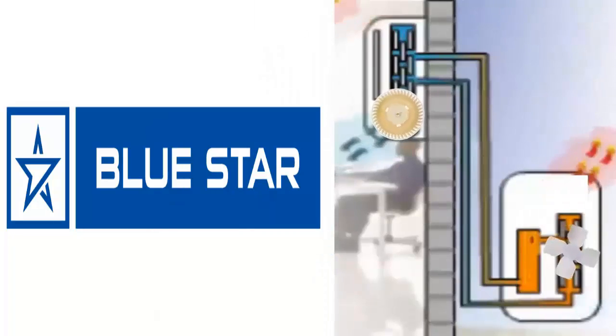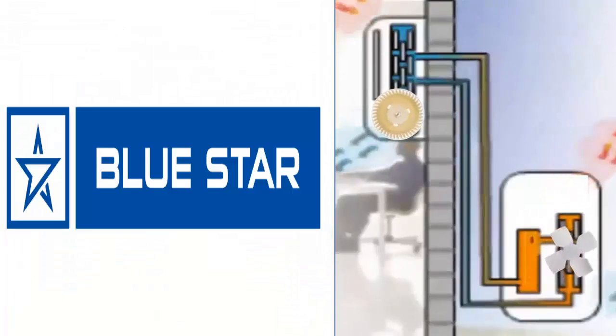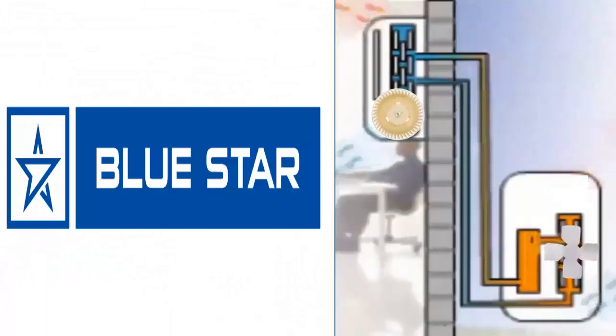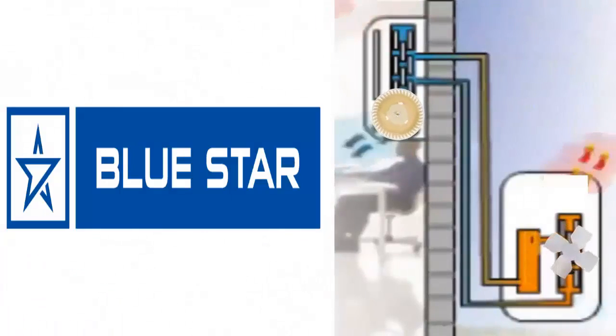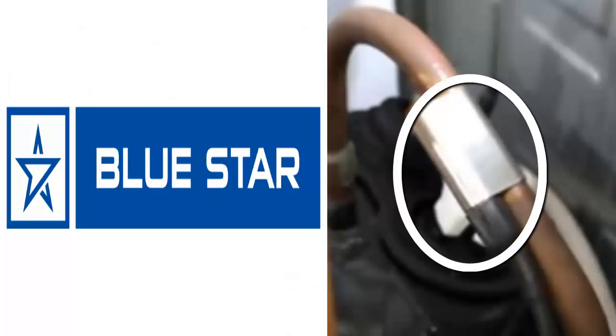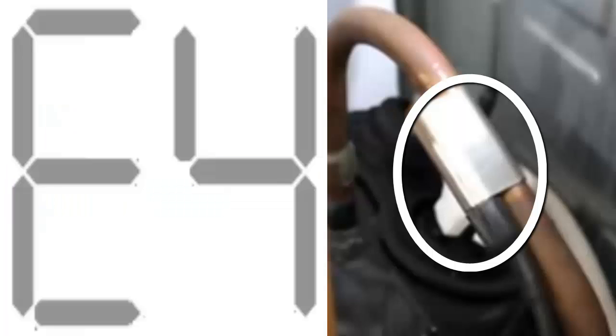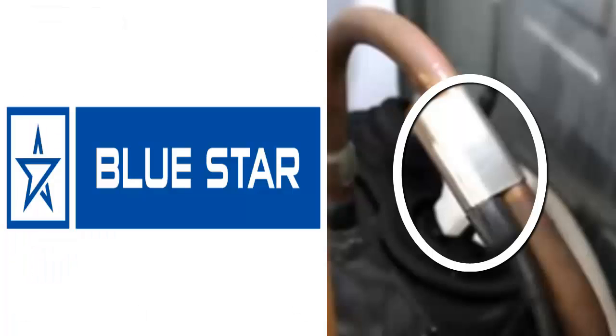Code F5 indicates a problem with the refrigerant discharge temperature sensor at the compressor outlet. This sensor is positioned on the thinner compressor pipe in the outdoor unit. In some models, if the problem is a much higher than normal discharge temperature, error code E4 will appear. In this case, it is recommended to check the correct rotation of the outdoor unit fan, rule out refrigerant gas overcharge, and check the cleanliness of the outdoor coil.